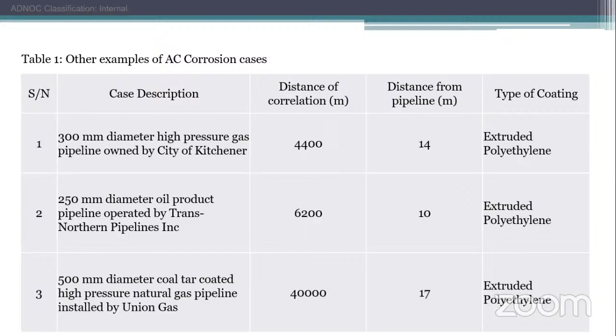So there's a problem in Nigeria specifically, narrowing it down to the country, because we've given instances of cases that have happened outside Nigeria. In our own Nigeria, we have laws restricting public utilities to common corridors for the common good, to reduce the cost of compensation, to make surveillance and management easy, and to limit impact on wildlife. So we are predisposed to this case of alternating current corrosion, because pipelines are, for good reason, placed by law in a common corridor with high voltage transmission lines.